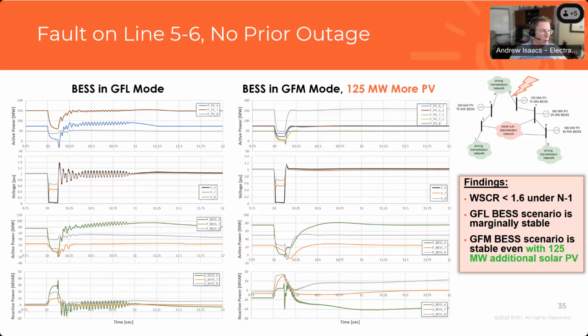It is still limited, and one thing that wasn't really highlighted in the discussion is that there were many times some type of thermal or voltage issue would have to be addressed in addition to these stability problems. It's not always the case that you find yourself right at the edge of the instability condition; there are conditions where that N-1 instability is the limiting factor. But you also have to consider: am I within voltage limits post contingency, do I have thermal overloads, can I even pump 500 megawatts of power through this weak grid based on a normal PV curve type situation? We were considering that, and we did run into it a few times throughout the study.